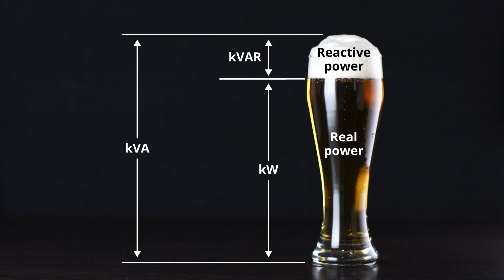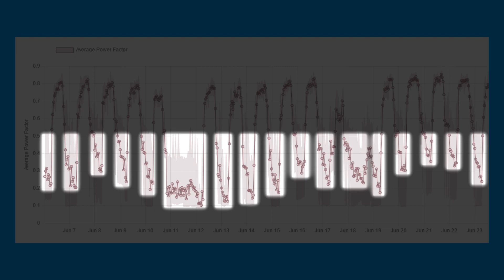Bearing that in mind, we can see from this transformer monitor graph that the building power factor is very poor overnight, as seen in the dips in the graph. The technical reason for this is that the various heavy equipment transformers in the building require magnetization energy, that's VARs, all the time. Since we're not loading it with our workday activities at night, all that's left overnight is the froth on the beer. This makes power factor lower.